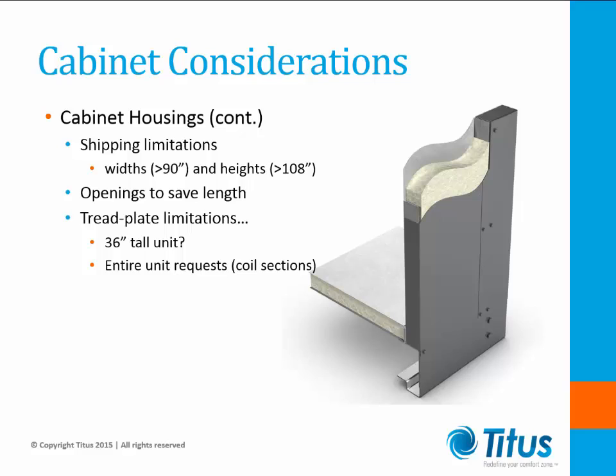Another item to observe is avoiding cabinets wider than 90 inches. Cabinets wider than 90 inches tend to require shipping splits and overwidth shipping charges. Trucks are 102 inches wide, and cabinets wider than 90 inches are likely to have shipping widths wider than 102 inches due to accessories mounted on the exterior of the unit, such as VFDs or disconnects.